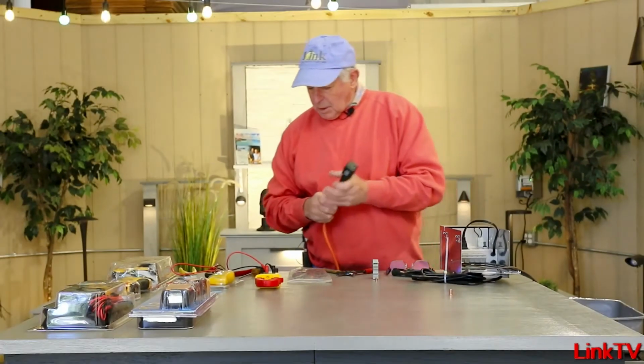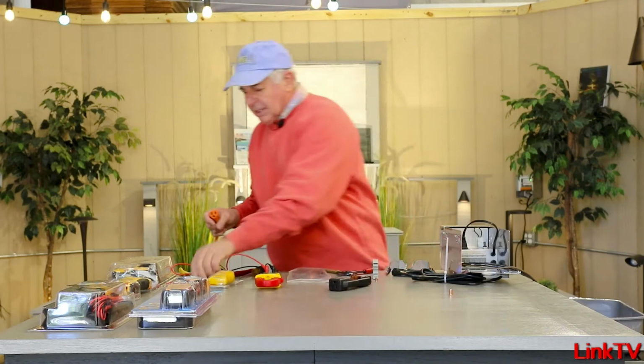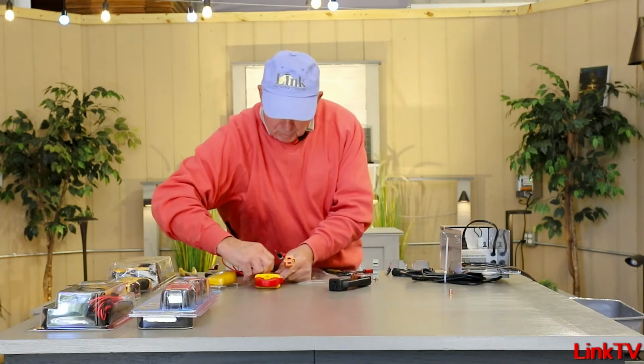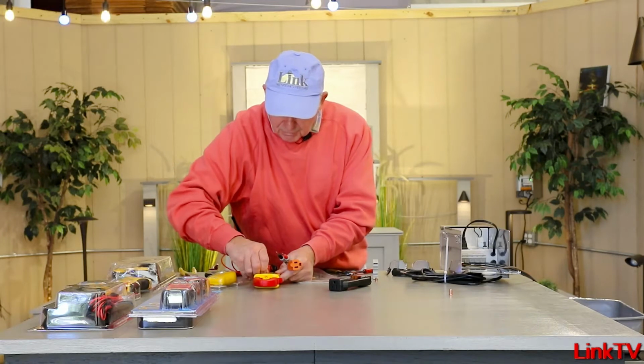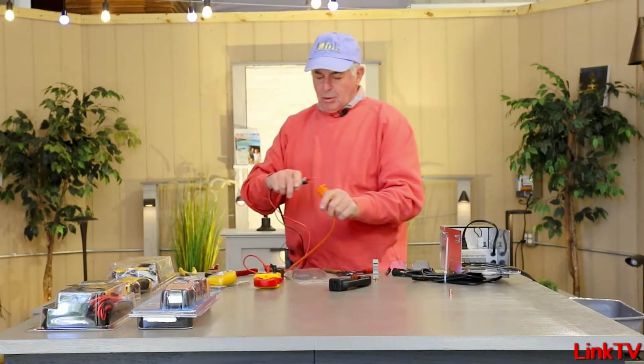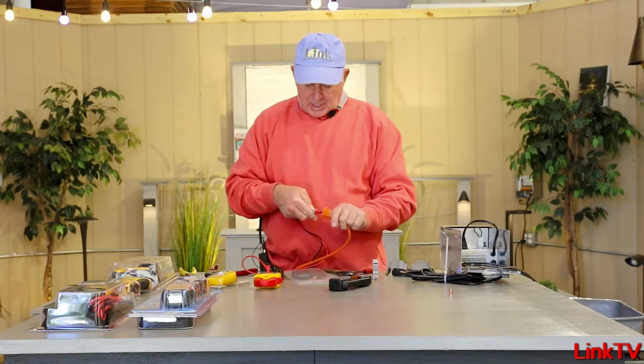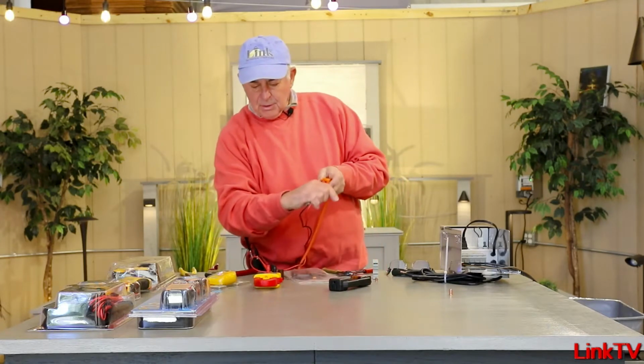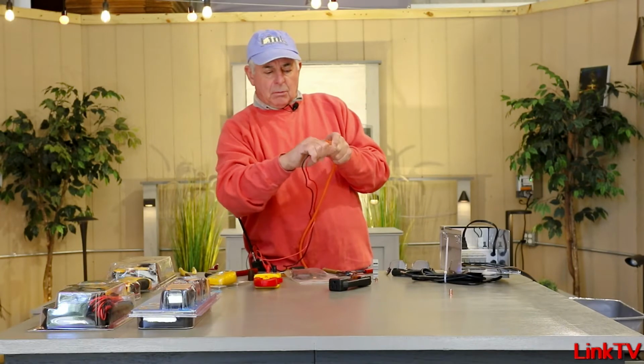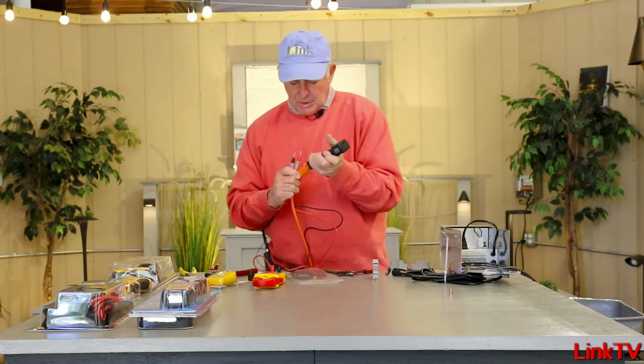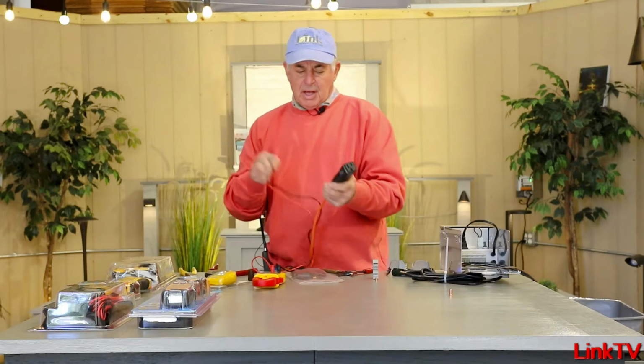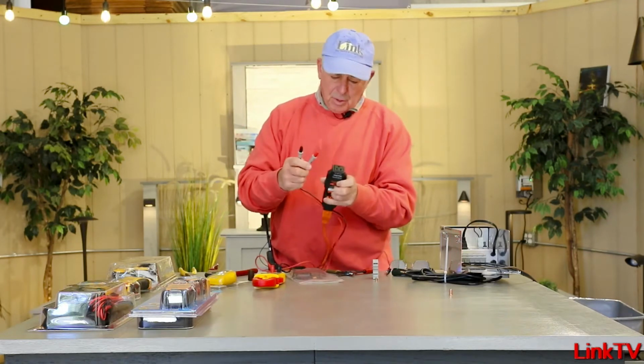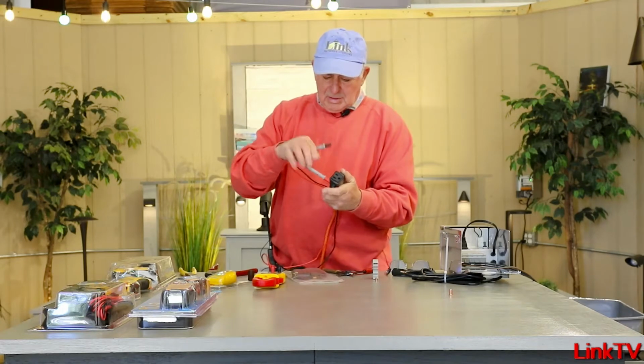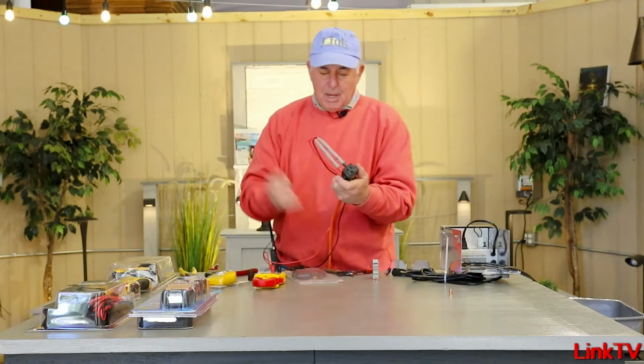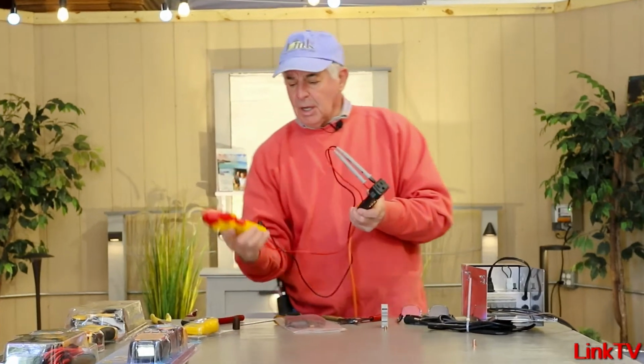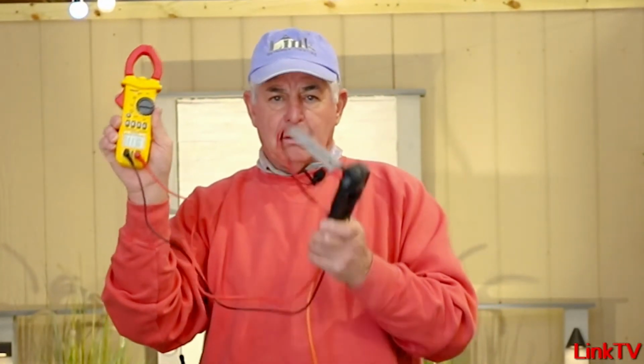Number two, have you guys ever had an issue where you're trying to read volts, primary side or even secondary side, you've got your probes, you stick them in, and you can't get an accurate reading - it bounces all over the place. Well, here's what you do: you insert this into that receptacle, and then you put your probes in right here. This is made just for that, just for your probes, and you can get an accurate reading.